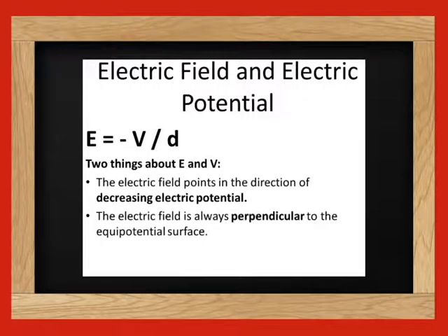When dealing with bare conductors, remember the equation E equals V over D, where E is the electric field, V is the voltage, and D is the distance. This is especially important with bare conductors, because if they come too close to each other, the air, which acts as the insulator or dielectric material between the two conductors, will break down, because the voltage would exceed the dielectric strength of the air.